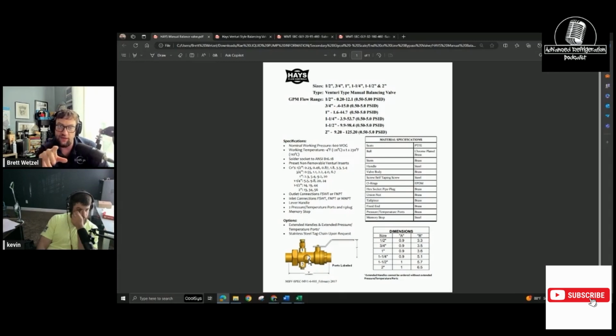And as soon as I did that, because I was just doing test runs since I didn't know what was going on, because they have this automatic formula within this Corel controller, which ramps up and ramps down, just trying to maintain a certain GPM. And it was maintaining, but as I slowed down the pump, I started getting more thermal conductivity. Then I got to a point where it was too slow and it started flooding out. So I was like, all right, something else is wrong. We're not getting enough flow in. And then we looked at that and I was like, oh, okay, let's close it down. As soon as we closed it down, we started getting the approach that we needed.